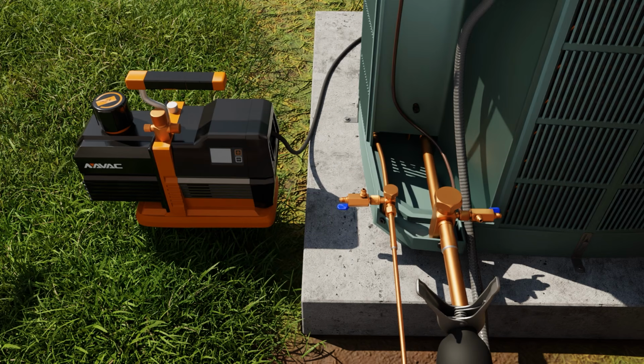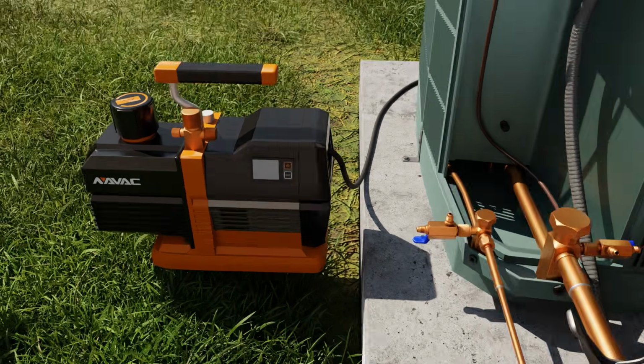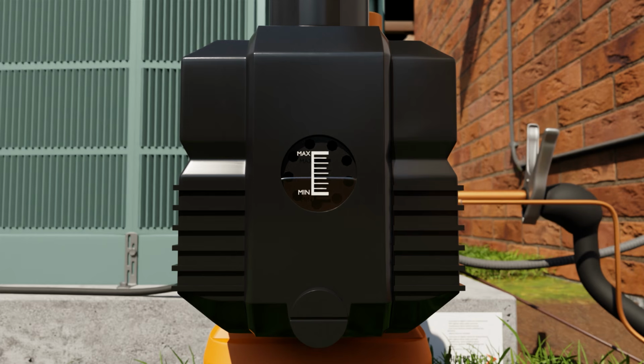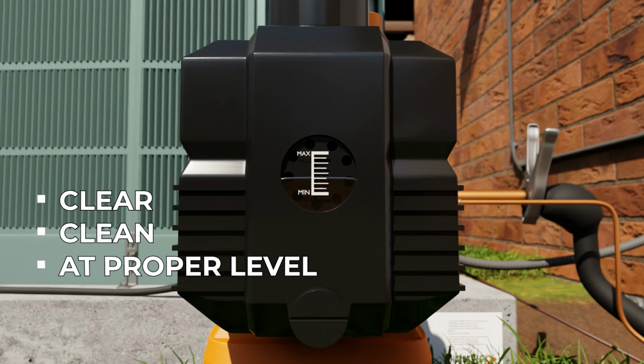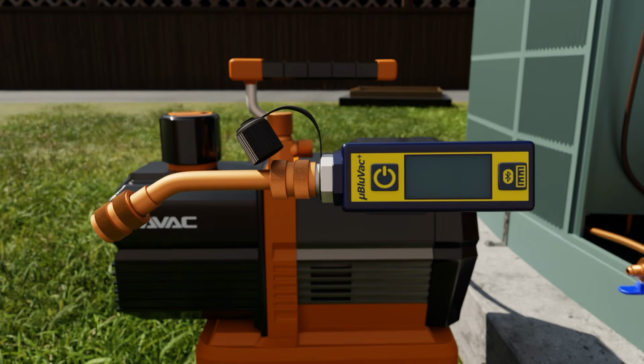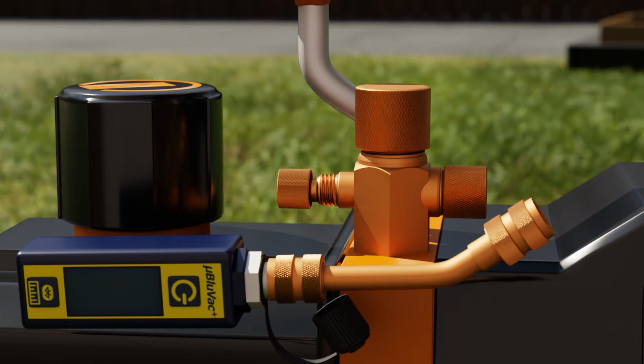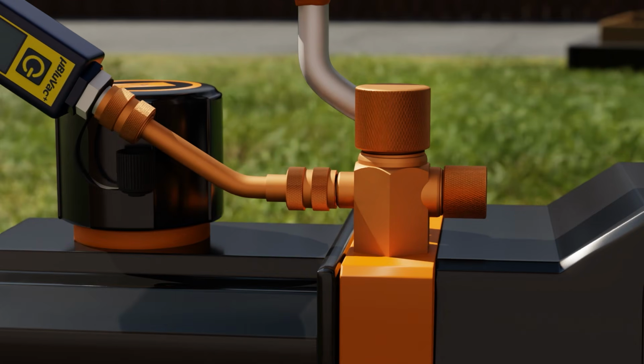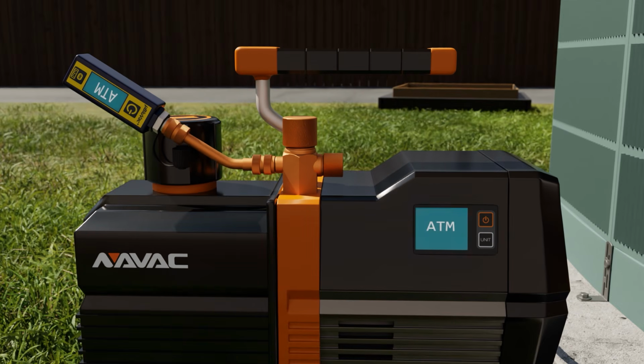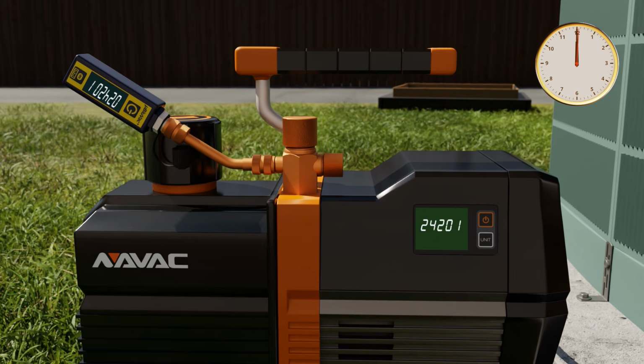Before you pull your vacuum, you want to ensure your vacuum pump is working exactly as it should. So step 1 is to check the vacuum pump oil to make sure that it's clear and clean and that it's at the proper level. If it's been a while since your last oil change, now would be a good time to change the oil in the vacuum pump. Next, take your vacuum gauge, often called a micron gauge, and hook it directly to the pump. You need to make sure the vacuum pump itself will pull below 100 microns in less than 30 seconds. This is typical. A good pump will even pull down to 30 microns or less than that.